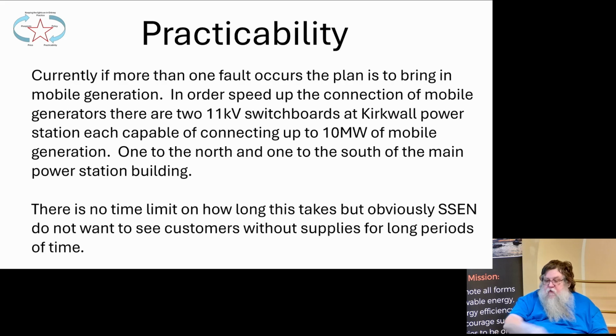Currently, if more than one fault occurs, the plan is to bring in mobile generation. There's two switchboards at Kirkwall Power Station where we can connect up to 20 megawatts of mobile generation, half to the north side of the power station and half to the south. There's no time limit on this, so if they had to bring in 20 megawatts of mobile generation, they might be able to find 5 megawatts based in Inverness and 5 megawatts based in Glasgow, and the other 10 megawatts at one time, when we asked where it was going to come from, it was going to come from Rotterdam and would take 72 hours to get to Orkney when I did an exercise back in the 90s. I don't know what the situation is now.